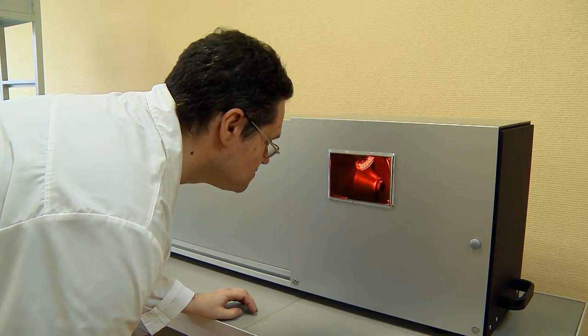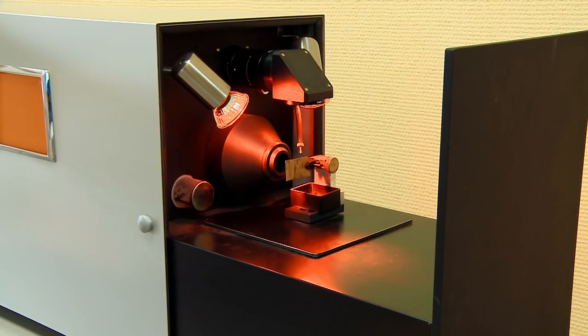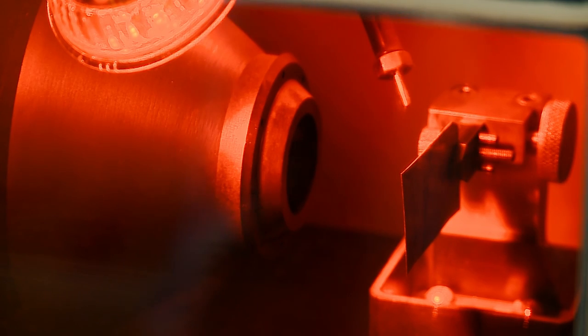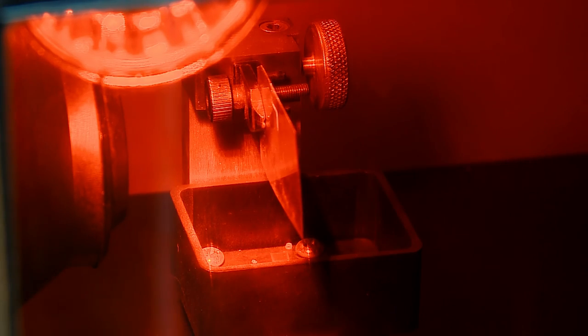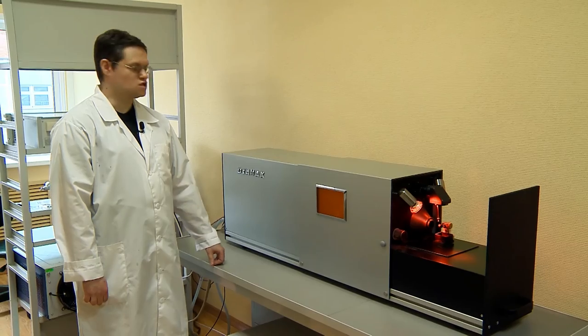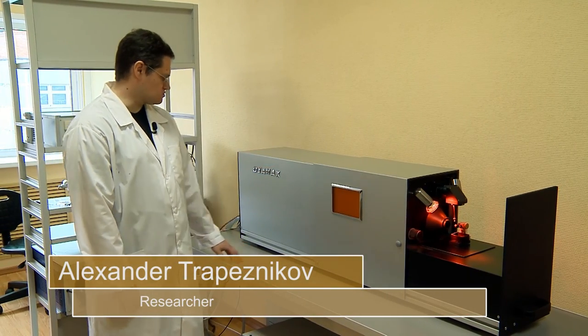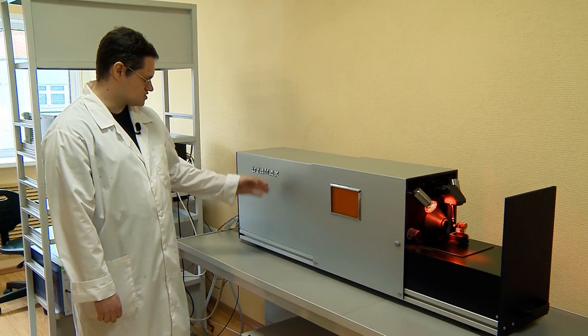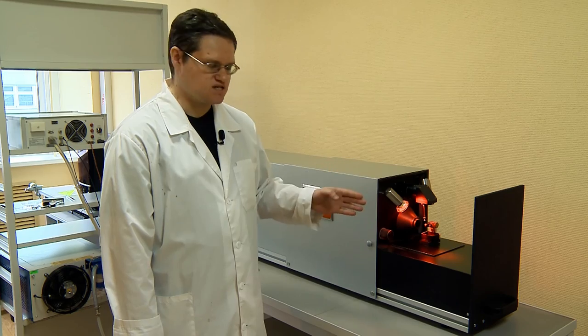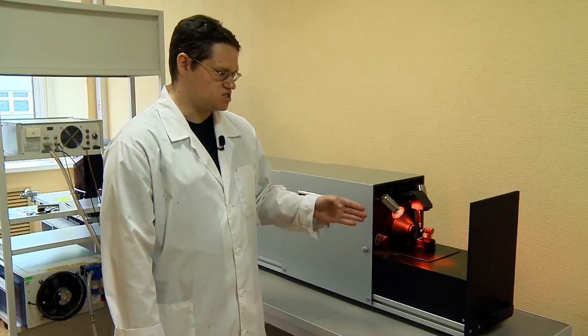In case defects are detected on the analytical complex, a crystal undergoes extra refinement. If it is possible to use part of the diamond plate, non-defected zones are cut out of the crystal. At this stage of detector manufacturing, single crystal diamond plates and respective metal furniture are cut via a special laser complex, correct to hundredths of a millimeter, for diamonds, sapphires, and metal plates.